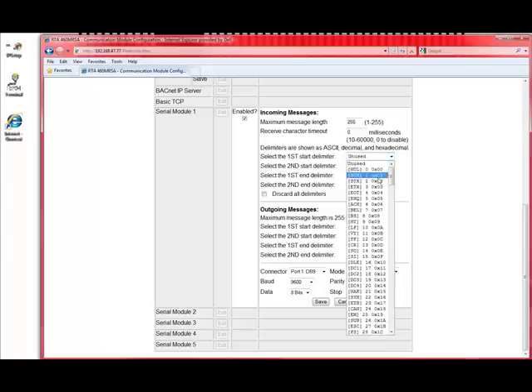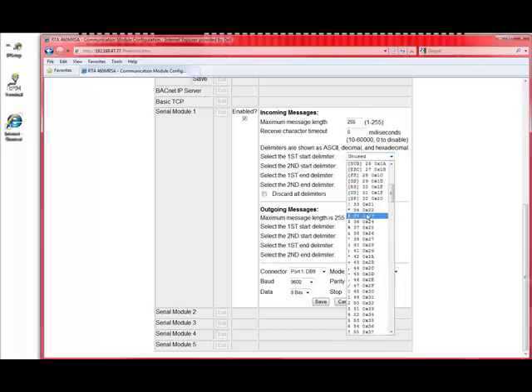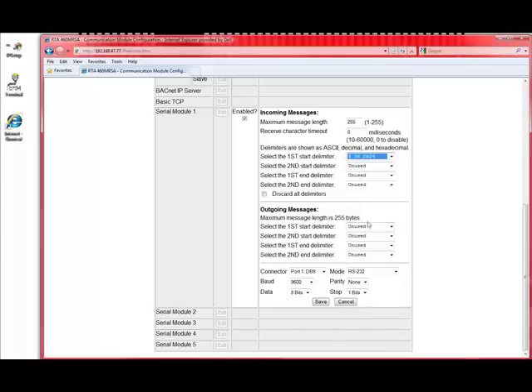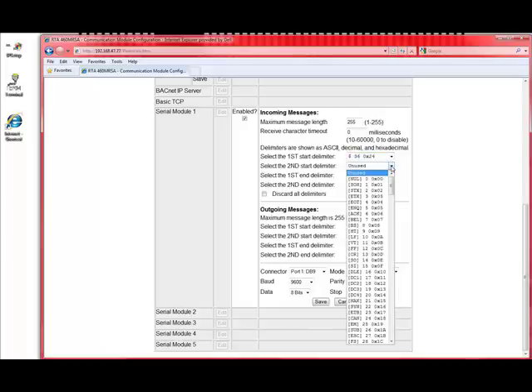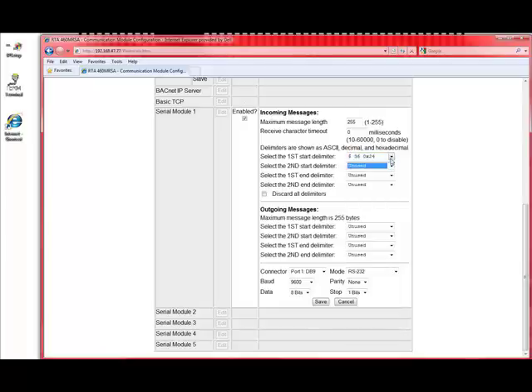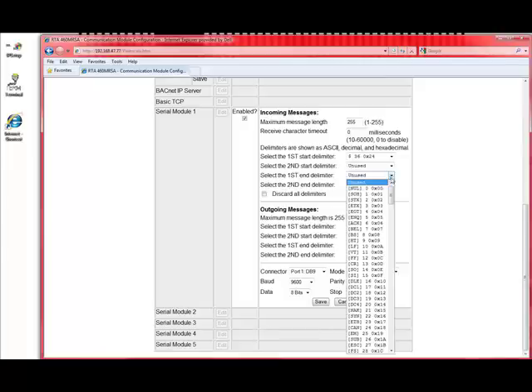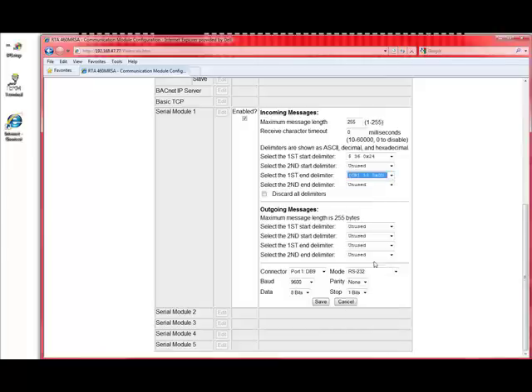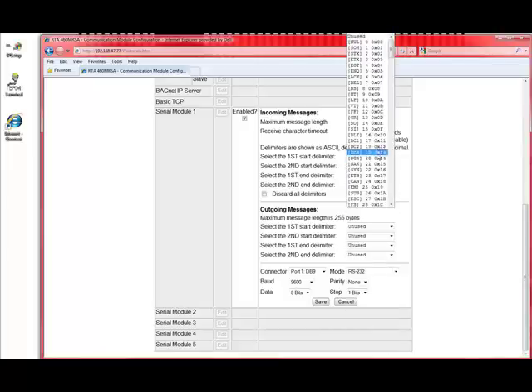But generally, that doesn't work very well if you have characters that come in at different times, as you would with, say, a barcode reader. What works better is to select a delimiter. So, let's say, for instance, that every time you start, you're going to start off with a dollar sign on the message coming in, and you could have a second character. We're not going to select a second one, but we're going to say every message starts with a dollar sign, and it ends with a carriage return followed by a line feed. So now that configures our incoming messages.